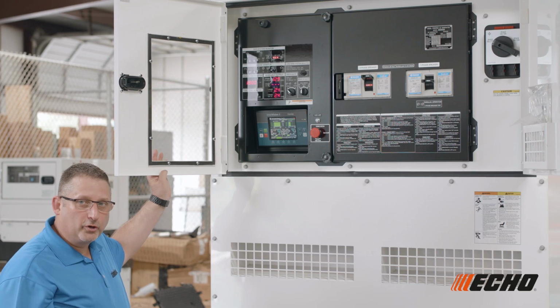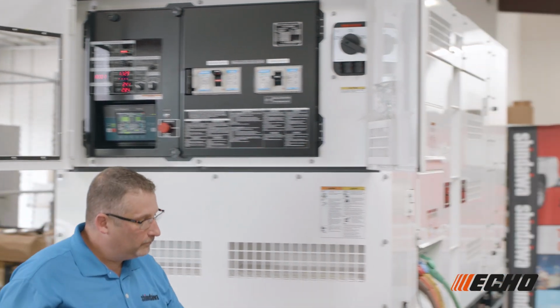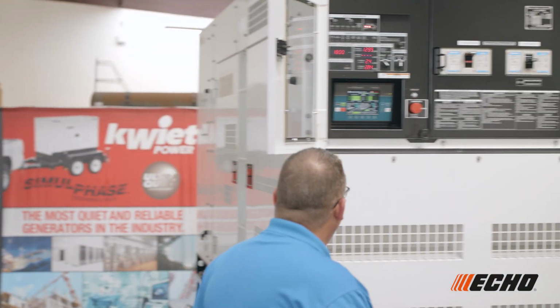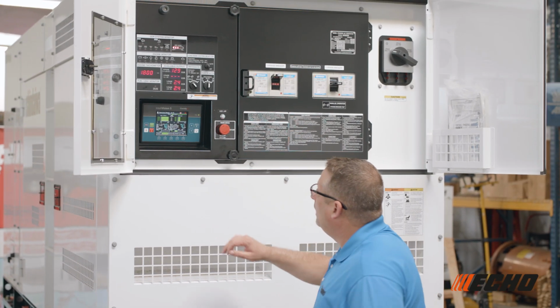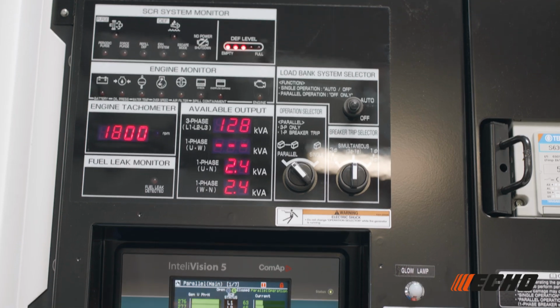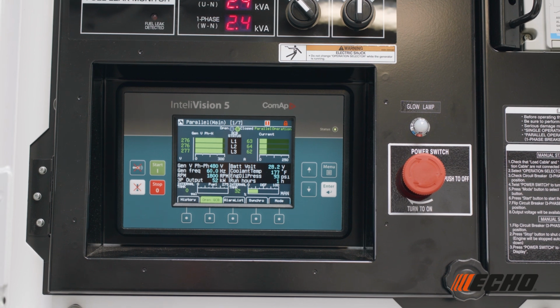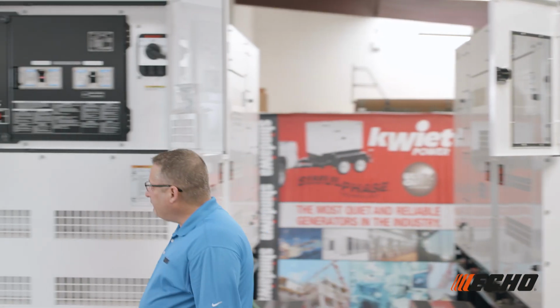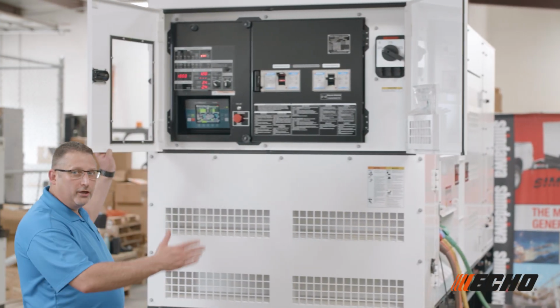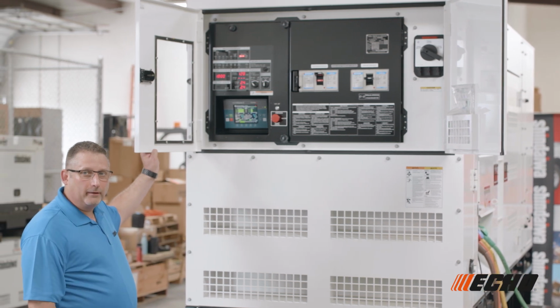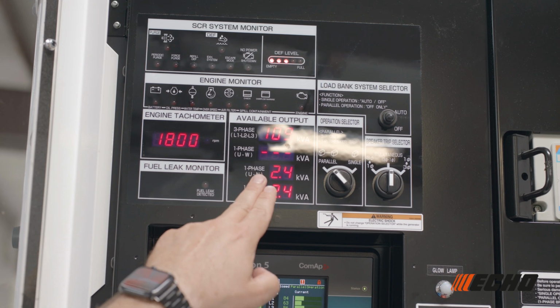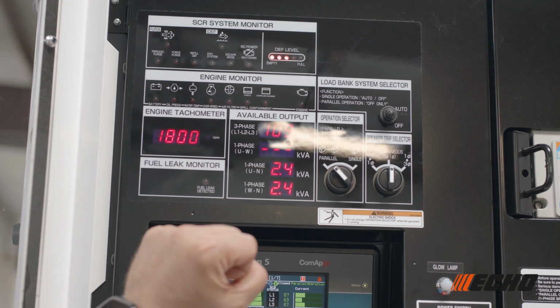Now we're going to go over to gen number 2. Gen number 2 has 129 kVA remaining, and we're running about 65 amps per leg. We're going to go ahead and add 50 kW of load, and you'll see where they share the load amongst each other. Both machines are now sharing that 50 kW. You'll notice we have 109 kVA of load remaining, and they're now sharing the 50 kW of load.